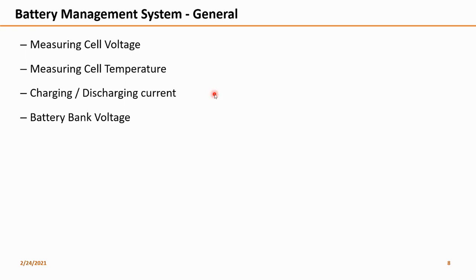We faced this. I worked in a thermal power plant where if there is any blackout, for example we are operating a 400 kV system connected to the grid. If there are issues in the grid, there are multiple prime running motors, or lube oil skids, multiple things which run on DC power. Also the UPS feeds power to multiple stations like DCS, where the battery management system plays a major role in monitoring.